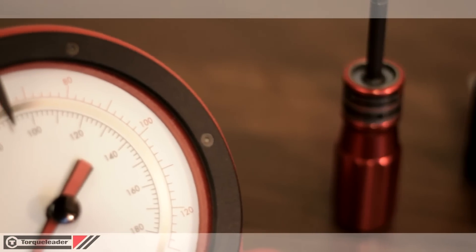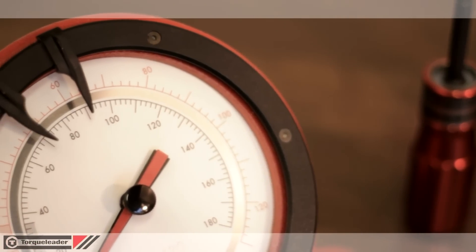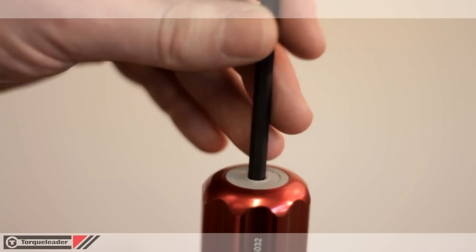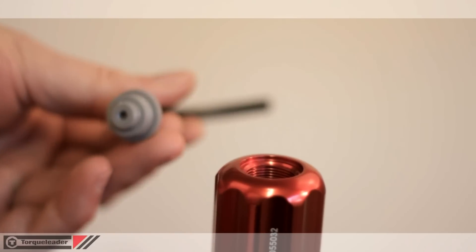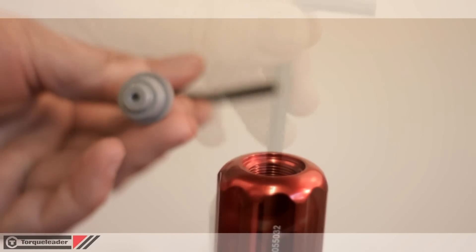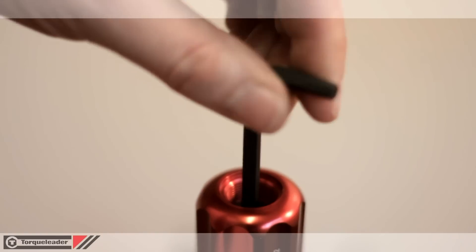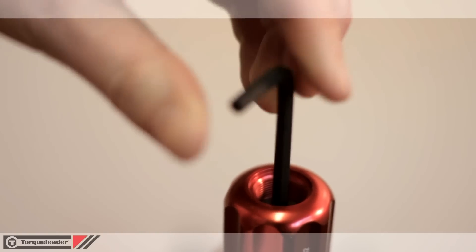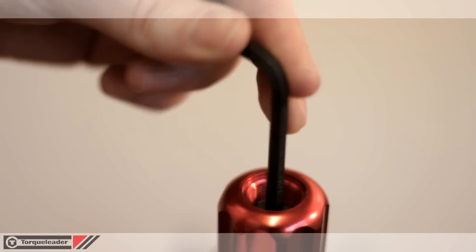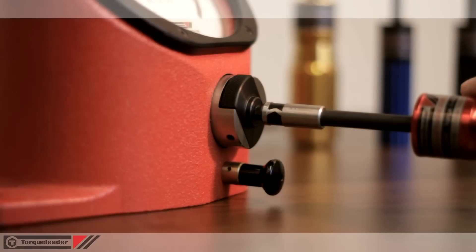Torque adjustment is made using either an analogue or digital torque analyser, in this case a Torqueleader MTS model. Removal of the dust cap reveals the adjusting screw. This is simply rotated using a 3/16 hexagon key until the correct value is shown on the analyser.